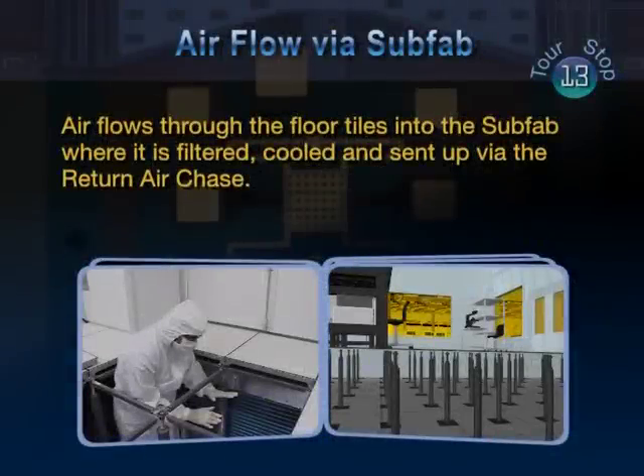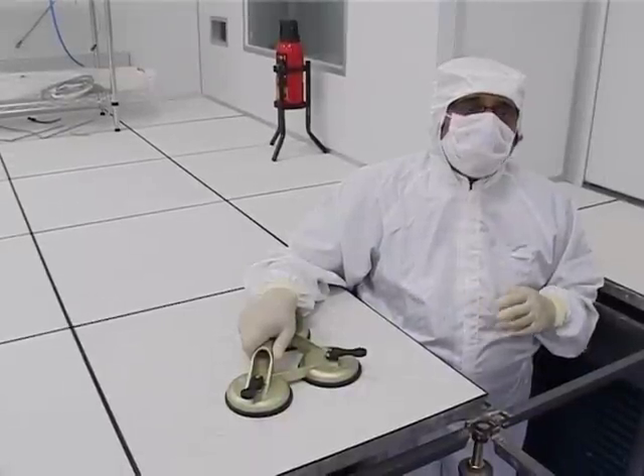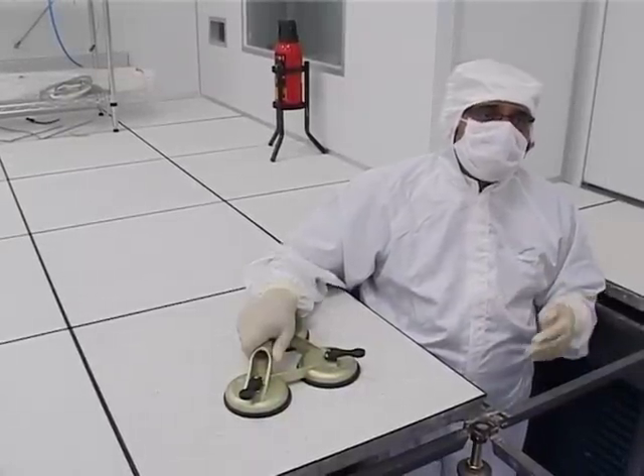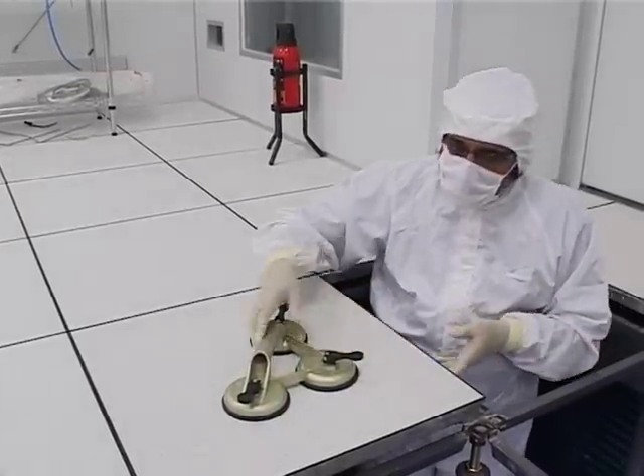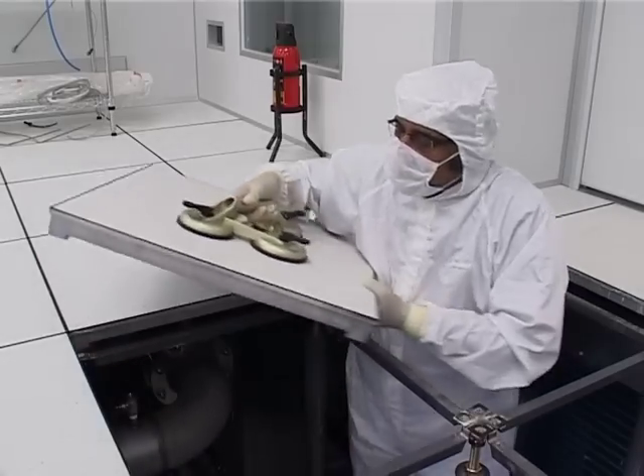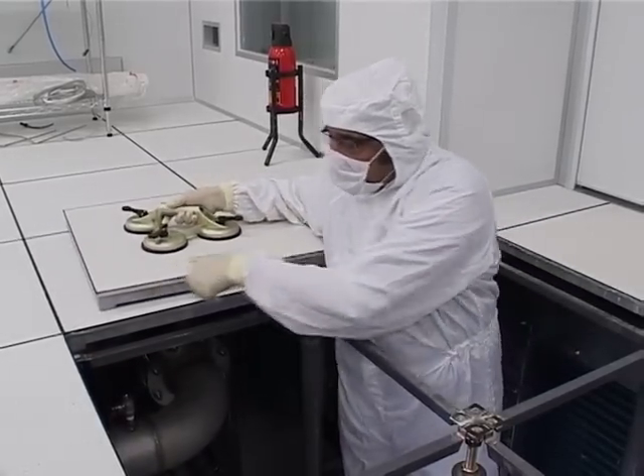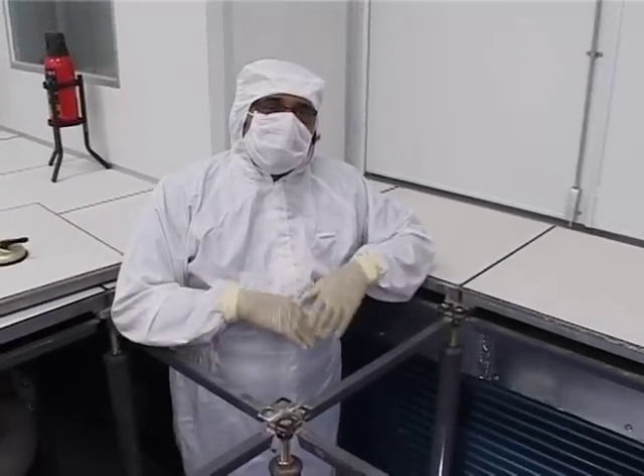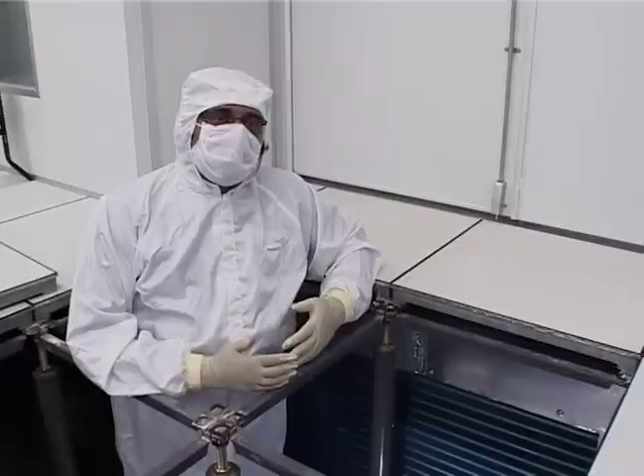Finally, let's step into the subfab and see how air flowing through the floor tiles comes here, is filtered, cooled, and then sent up via the return air chase. I have removed 3 floor tiles from this cleanroom area. Now I am removing the 4th tile to have better visibility. I am now standing inside the subfab area, or the basement, of this cleanroom facility.